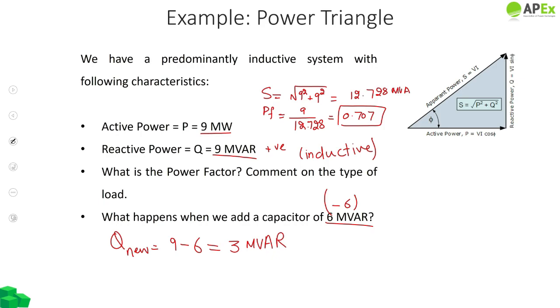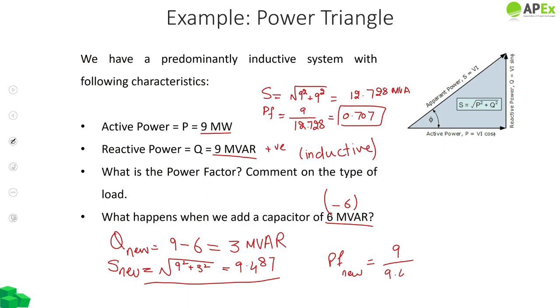Now we will find the new apparent power after applying the capacitor. This becomes the square root of 9 squared plus 3 squared, which works out to 9.487. Our new power factor is the active power, which is 9, divided by the new apparent power, 9.487, which works out to 0.95 lagging, because the reactive power is still consumed by the system, in the order of 3 megavars.